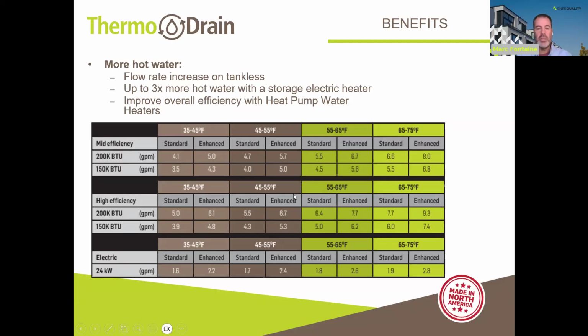And these devices usually are sized based on the lowest cold inlet temperature of the year, so that they can supply the correct flow rate of hot water as needed. So we have an example here where we have a 4 gallon a minute supply capacity for an instant water heater without drain water heat recovery, and then with drain water heat recovery, we go up to 5 gallons a minute. So there's a 25% boost in available flow rate when combined with drain water heat recovery.